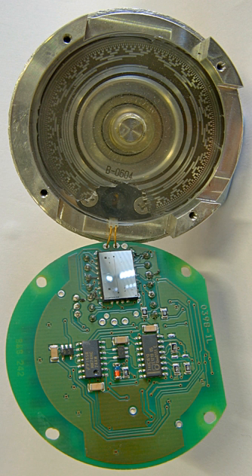Topic: Absolute multi-turn encoder. A multi-turn encoder can detect and store more than one revolution. The term absolute multi-turn encoder is generally used if the encoder will detect movements of its shaft even if the encoder is not provided with external power.